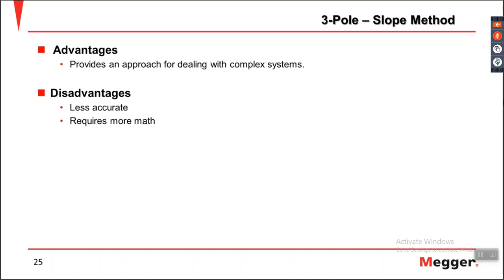They tried to do some research, and this method can be used for testing ground resistance. It also requires more math because you need to do calculation and look at the table to define it. But if you are already familiar with this method, I think it will be fast and efficient for testing your ground system.